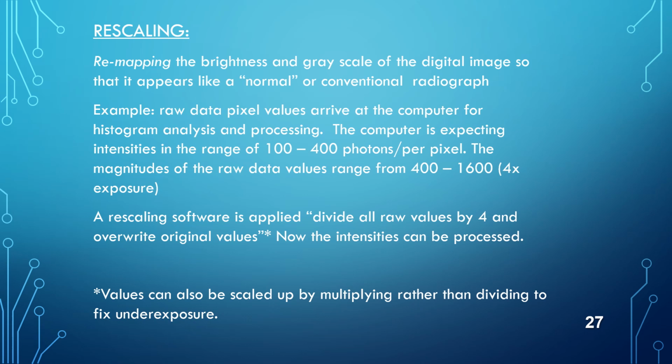And so what really happened with the density plus? Well, you ran the exposure longer. And so what does that mean? Did you change anything? No, the computer corrected for it. It literally reversed the change that you made when you selected density plus.